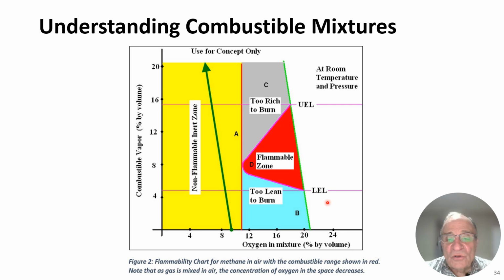This lower level is called the LEL, lower explosive limit. This upper level is called the UEL, upper explosive limit. And in between is the flammable range. Now that flammable range gets smaller and smaller as you have less oxygen in the environment. So let's say I started with a room that was at 16% oxygen content, and I go up in this direction, and my flammable range now starts at around 7% gas in that room's environment. I keep going up and I'm going on an angle. I get to maybe 11.5%, and that's my new flammable range.